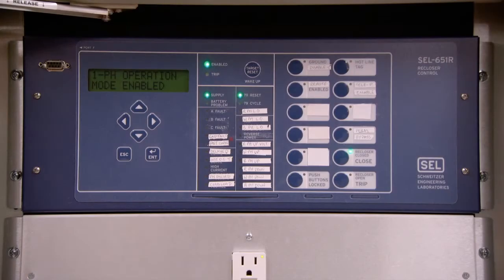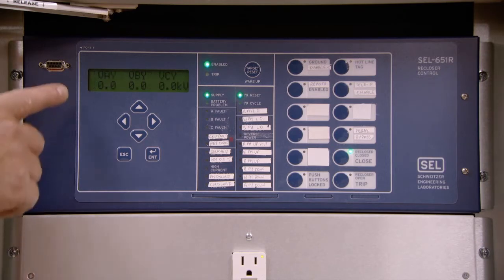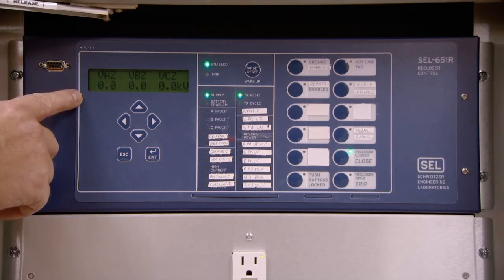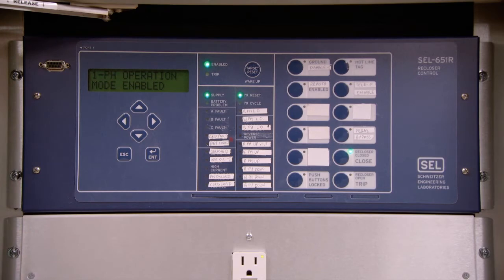The scrolling screen. When you open up the control cabinet, you'll see a small green LCD screen. This display will cycle through the different functionalities of the actual control. The scrolling information on the highest level menu tells us that this unit is set for a single-phase operation mode, and that it is also set to single-phase lockout. It also indicates the settings group, the amperage that it is supplying, and the voltage that is being applied to the line. This will be helpful when you're actually installing or removing these reclosers from service.